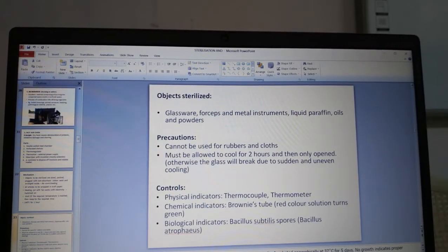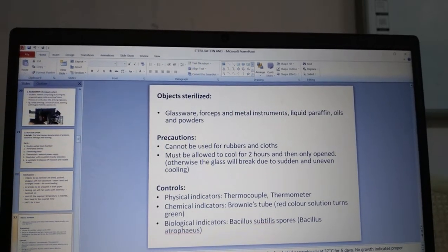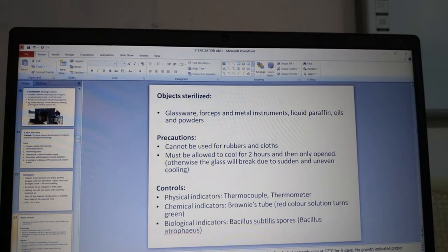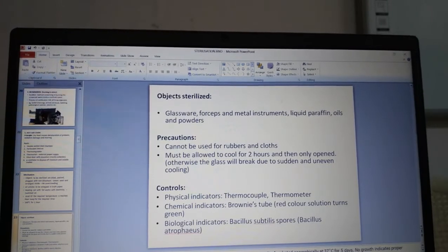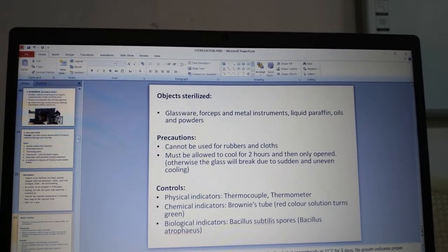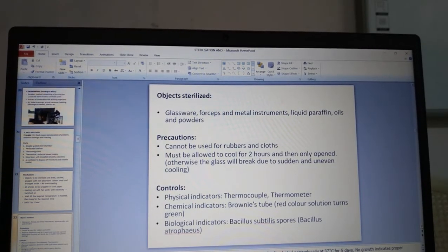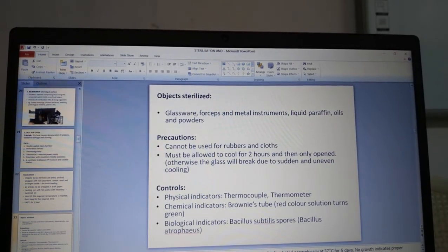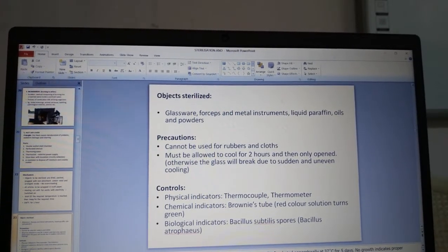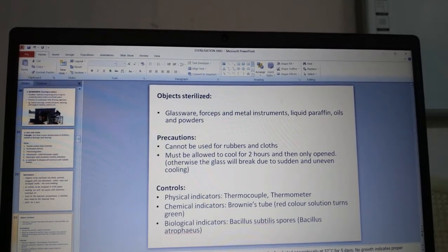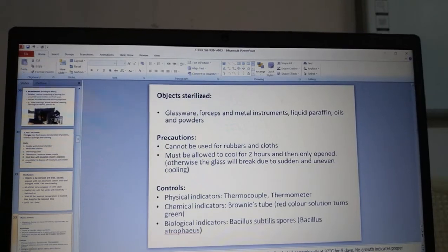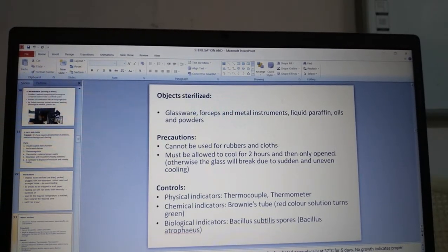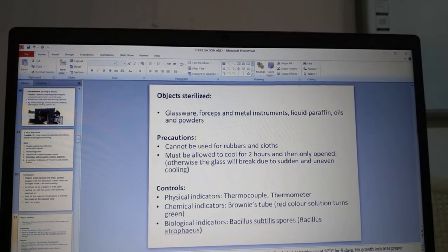Items sterilized in the hot air oven include all glassware — pipettes, conical flasks, slides — as well as forceps, metal instruments, liquid paraffin, oils and powders. Precaution: it cannot be used for rubbers or cloths, and the oven must be allowed to cool for two hours before opening. If you do not do that, due to uneven cooling, there is a chance of the glass breaking.